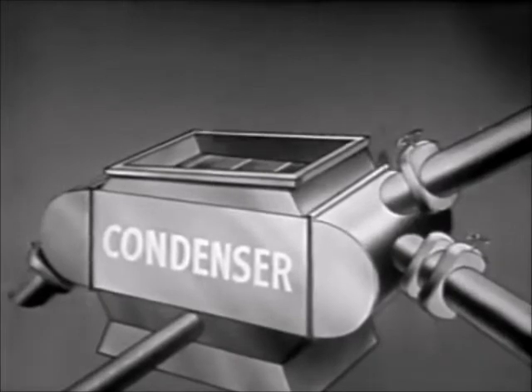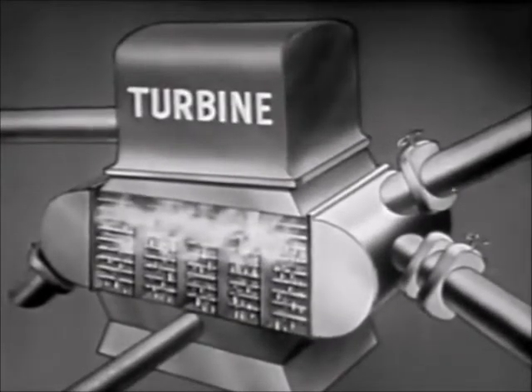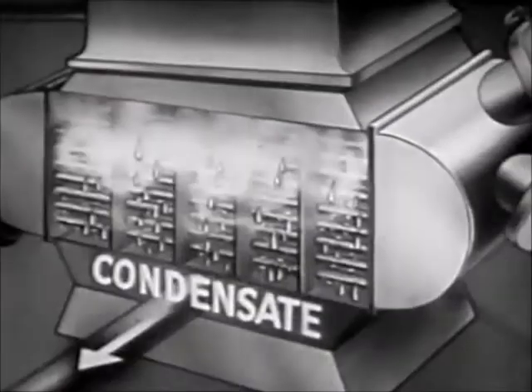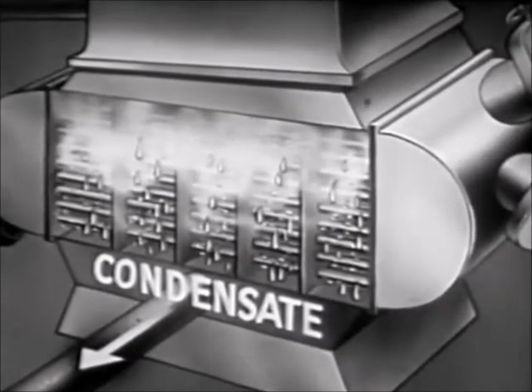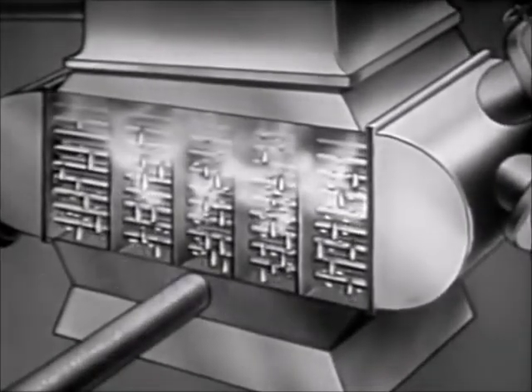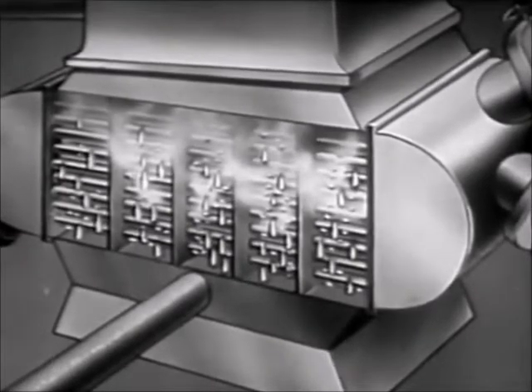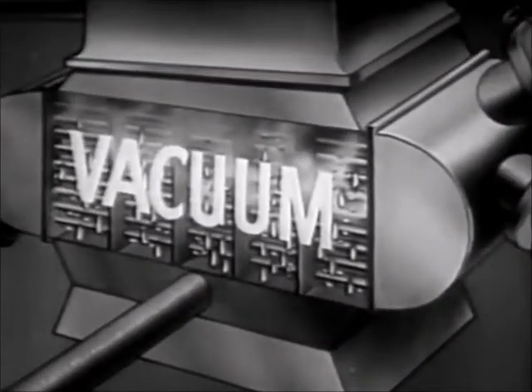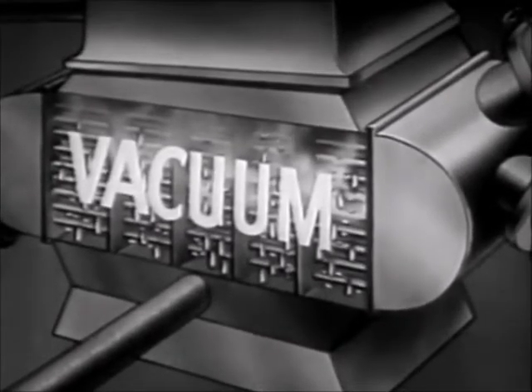An important example is a ship's main condenser, shown here in simplified form. This condenser recovers turbine exhaust steam as water, now called condensate, for reuse in the boiler. This is important because boiler feed water must be pure, and pure water is scarce at sea. In addition, because the recovered water occupies less space than its equivalent steam, a partial vacuum is created at the turbine's exhaust. This low back pressure adds to power plant efficiency.